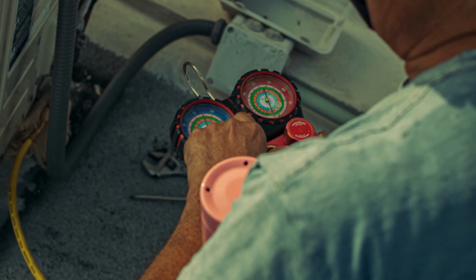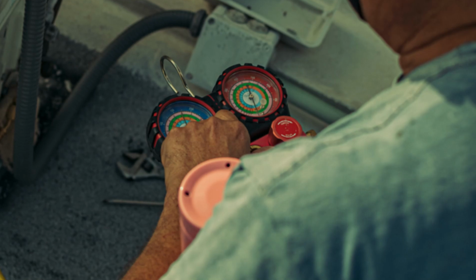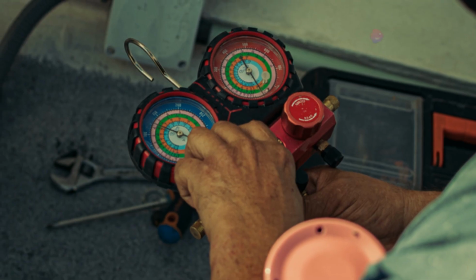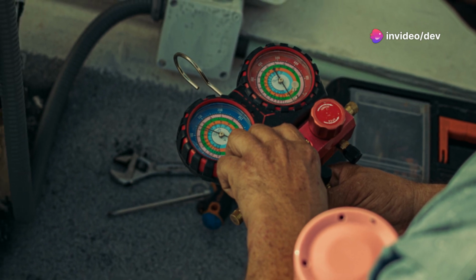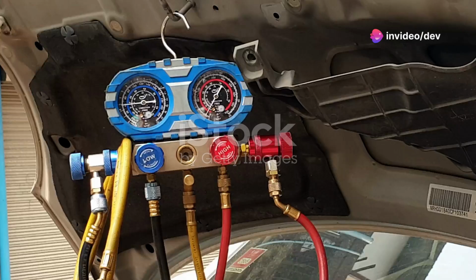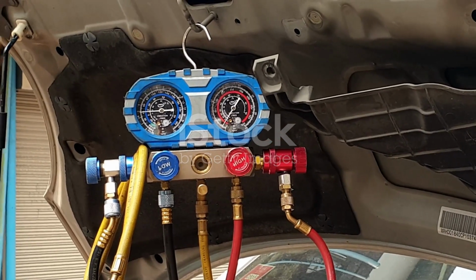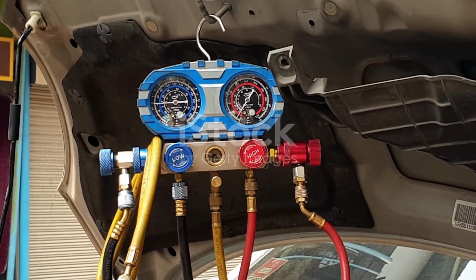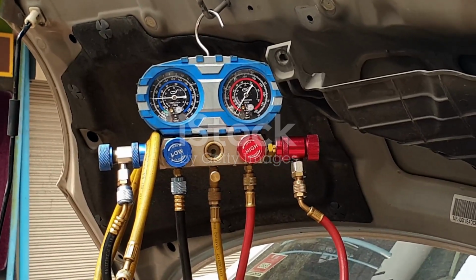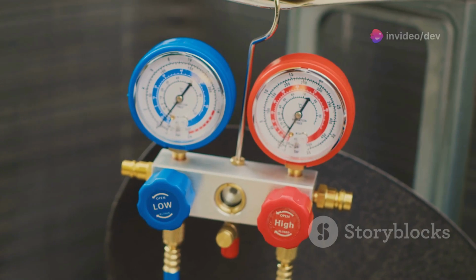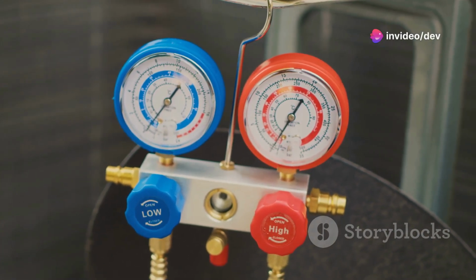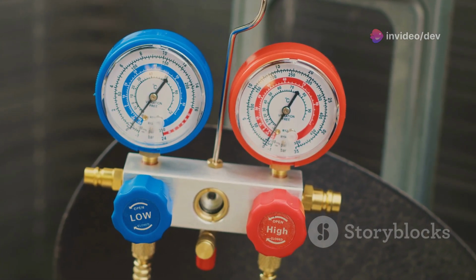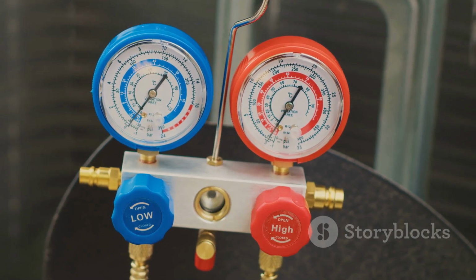Finally, it's time to check the refrigerant levels using your trusty manifold gauge set. Proper refrigerant levels are essential for the efficient operation of your AC system. Connect the gauges to the service ports on the compressor, following the manufacturer's instructions. Ensure the connections are secure to avoid any leaks. The gauges will display the pressure readings, which you can compare to the recommended levels for your specific AC system. If the readings are off, it may indicate a need for refrigerant recharge or other maintenance.